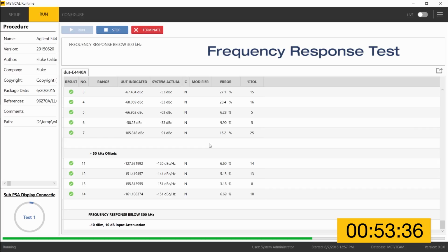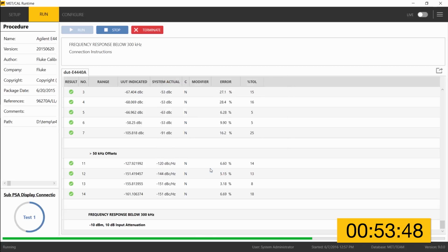And now we're having a connection instruction for the frequency response test, which asks us to connect the leveling head directly to the UT RF input. That is already in place from before, so I'm going to go ahead and click advance.